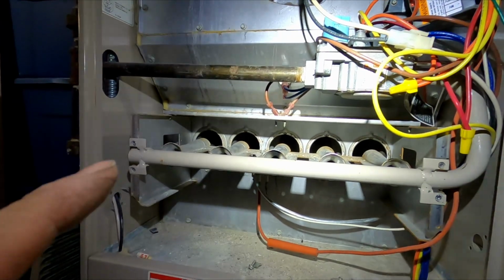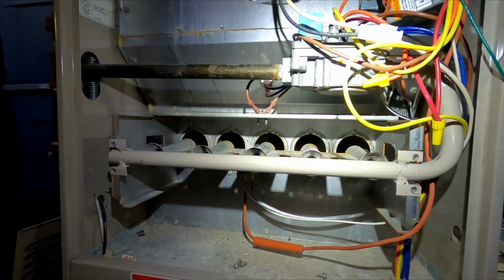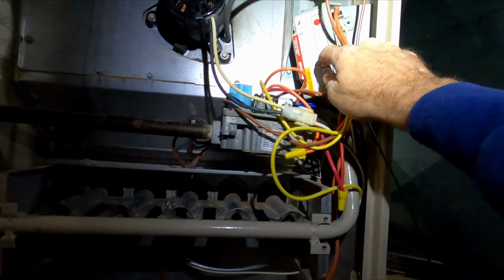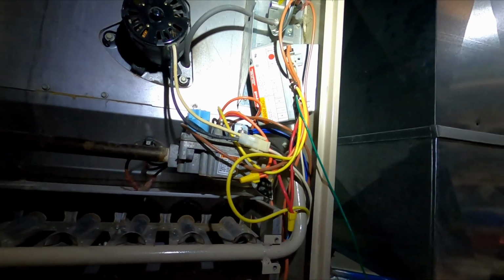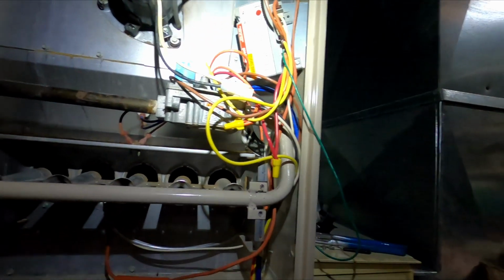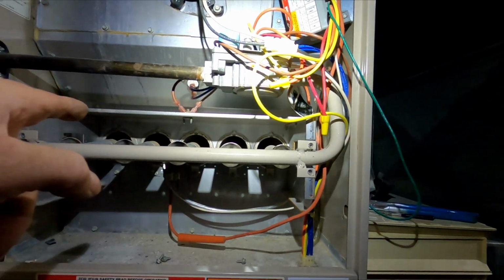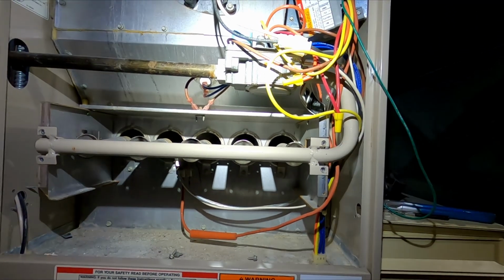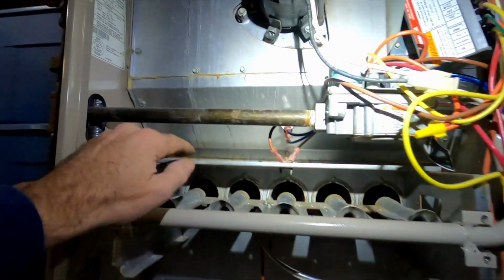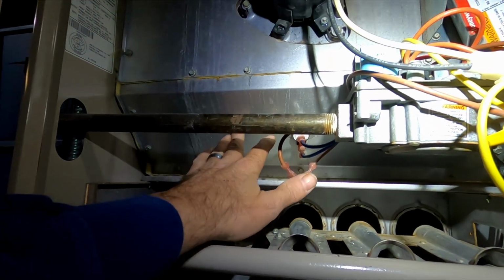Check the flame sensor, it's good. These are known to go bad. It's been changed before, but we're going to pull the burners too. We're going to take this plate off right here and do a heat exchanger inspection.